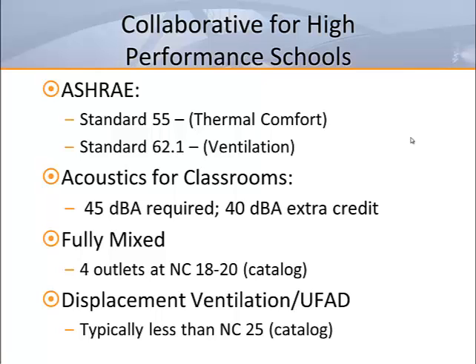CHPS's goal for selecting air outlets for a fully mixed system design is 4 diffusers at a maximum of 700 feet per minute neck velocity and a catalog rating NC of 18 to 20. This will allow for some additional noise created by multiple sources and field inlet conditions, with room results in the NC 25 to 30 level. Displacement and underfloor systems usually result in low NC levels of 30 or less in the space.